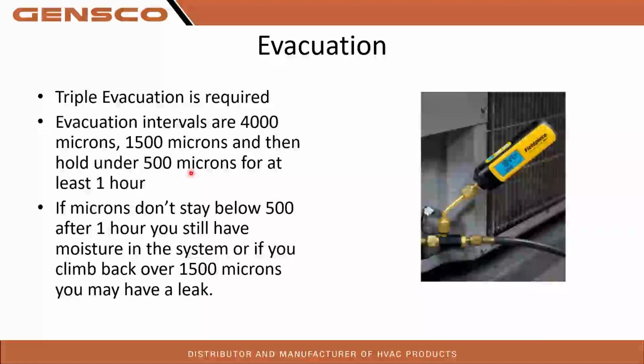If you end up coming up above that, say your microns rise to 600, 700, 800 microns or so, chances are it's because you still have moisture in that system. So if you do see that rise, put it back on vacuum and let it sit on there for a while longer. If you're going back up over 1,500 microns or breaking vacuum completely, chances are that's because you have a leak in the system. So probably a real small leak that wasn't caught.